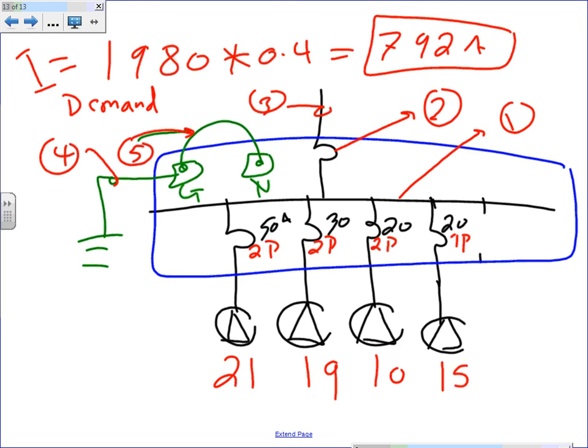Okay. And as long as you are in it here, Chris, you can open a can of worms. Let's go size single. This one will be most likely two conductors number 12. Done. Right? And if it's longer distances, you might put number 10 because of voltage drop. So be careful. This one, the same thing, two conductors number 12. This is two pole, two conductors number 10. And this one, 50, that will be two conductors number 8. Done.